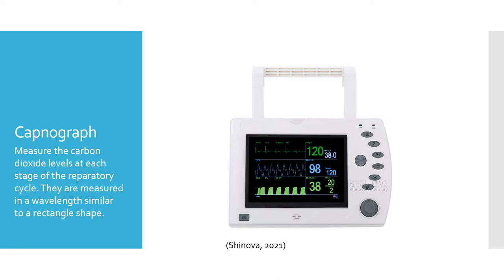When using a capnograph, it can detect lots of different equipment malfunction problems. While monitoring CO2 levels, it can alert staff to other complications that can occur at the endotracheal site, such as a leaking, deflated, kinked, or obstructed tube.